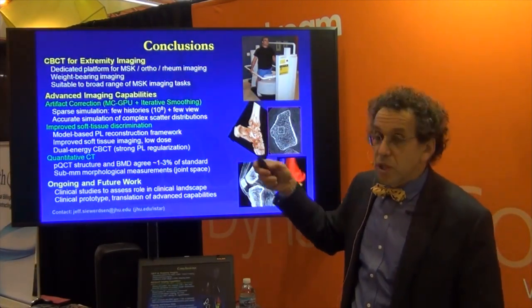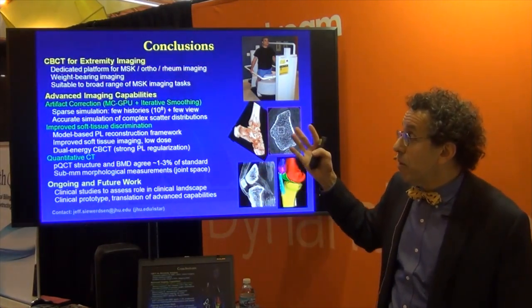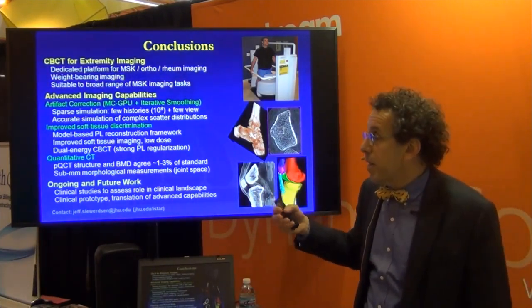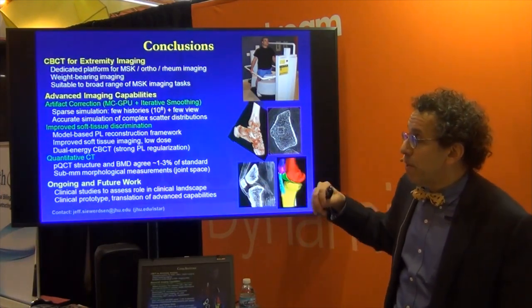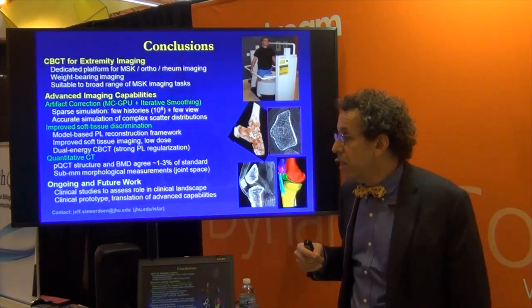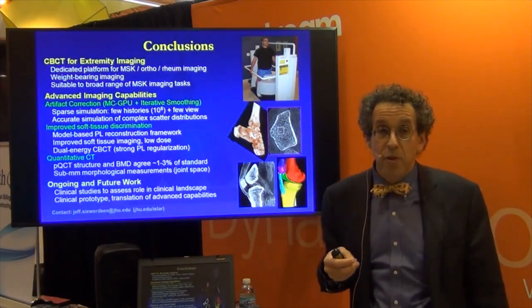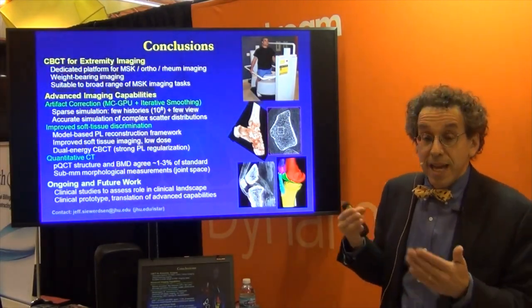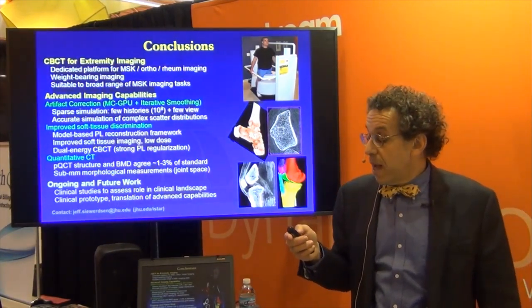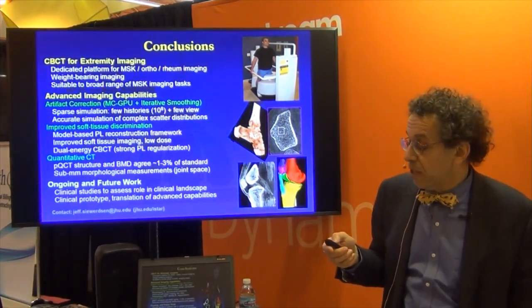In conclusion, the core technology: it's a dedicated musculoskeletal machine. It's portable — it can roll into an elevator, be set up, and plugs into an outlet. You have advanced image capabilities, artifact correction, metal artifact reduction, excellent soft tissue discrimination, a quantitative CT to judge bone density, and morphology assessment to judge procedures before and after they've been performed. This will hone in our skills and help us create additional more useful technologies and techniques.